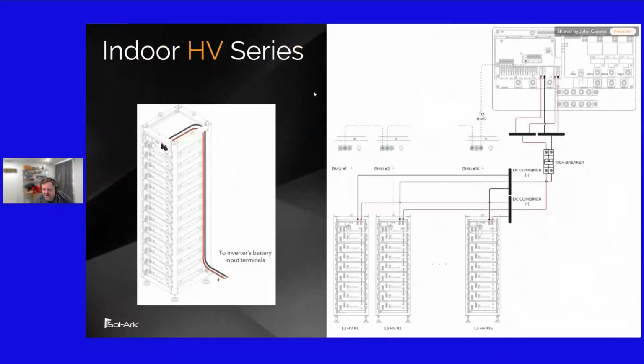The indoor series is designed for a controlled room. It's not designed just to be hanging out in an electrical room. It's an authorized person, authorized access only room. Conductors come out the side. You may or may not need a combining strategy depending on your configuration. If you do, the good news is now you're in high voltage, so high voltage, low amperage. There's a lot of solar combining products out there that can be utilized in this space.